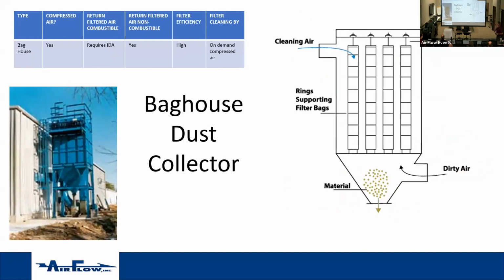Bag house, again, used for some larger CFMs. Dirty air will come in, same kind of concept as the other ones. You'll have your column of bags. A lot of times these bags will be in cages. They'll have supporting rings around them so they don't collapse. Clean air will go through and come out. The clean air that comes in on a bag house usually is either a compressed air that'll blow off the bags itself, or a blower that'll actually reverse that air back down and purge that air back into the bottom. Much bigger CFM. When you get into this stuff, you're getting into some industrial devices.